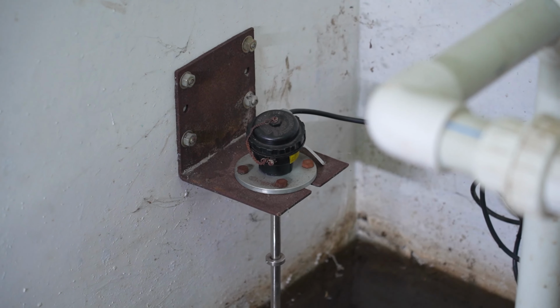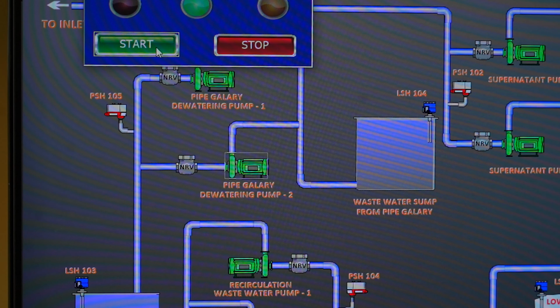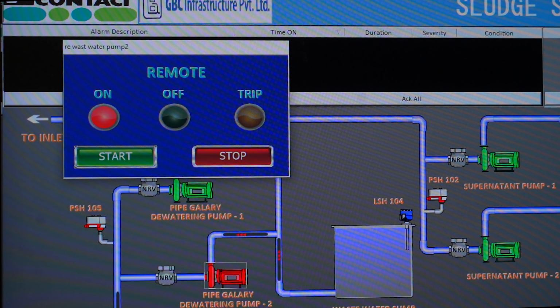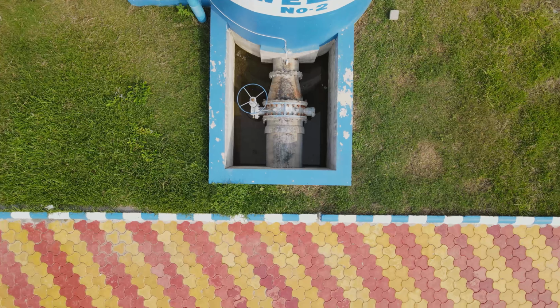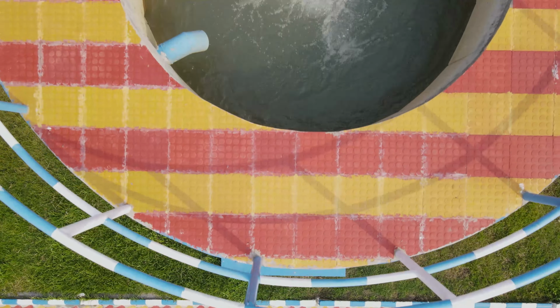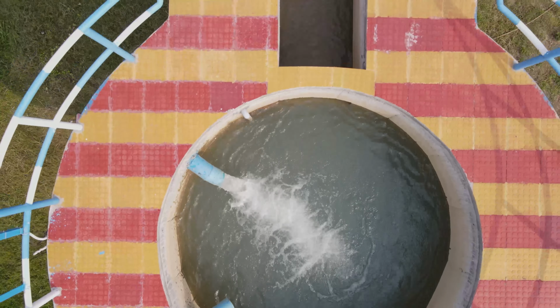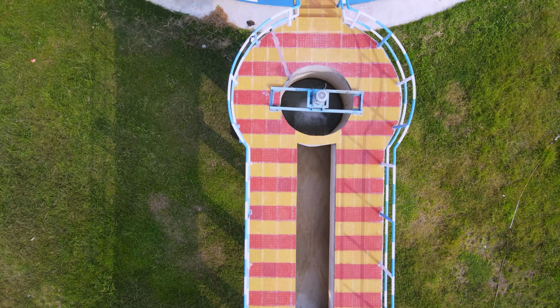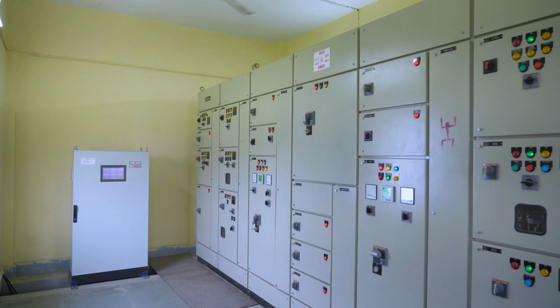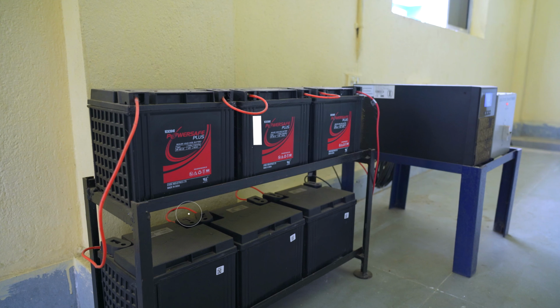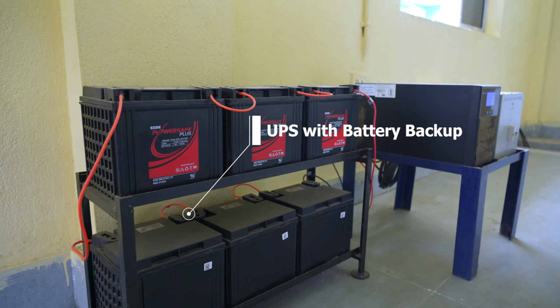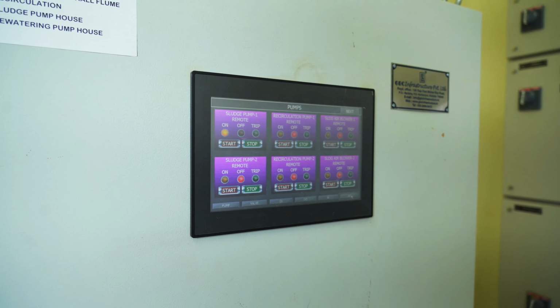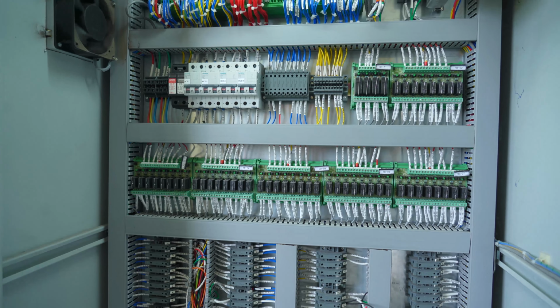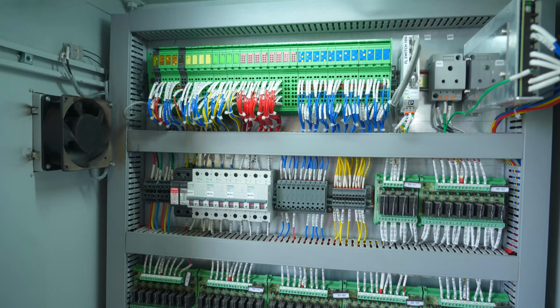The level of water in the sump pit at the pipe gallery is controlled by a level switch, and subsequently the dewatering pumps are operated from the SCADA control room. Recirculation of wastewater coincides with the flow of raw water into the inlet well. Power breakdown may happen. However, equipped with a UPS with a separate backup battery system, the RTU will continue running and immediately report a power failure alarm.